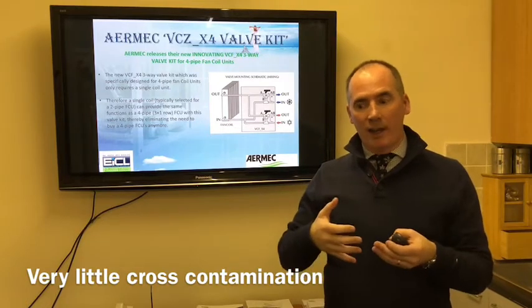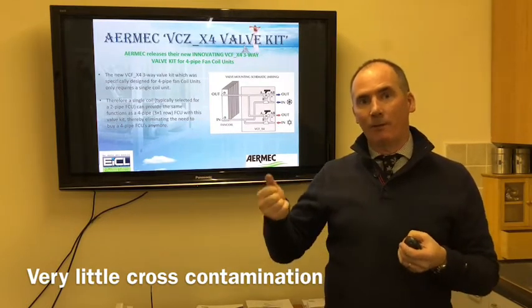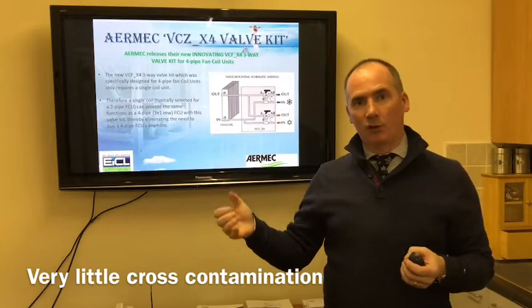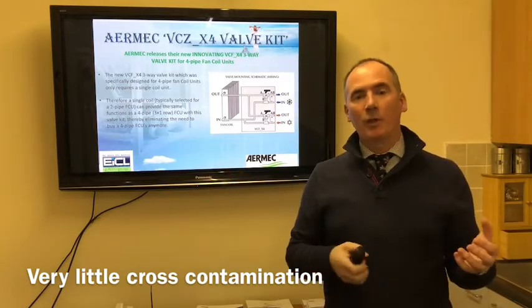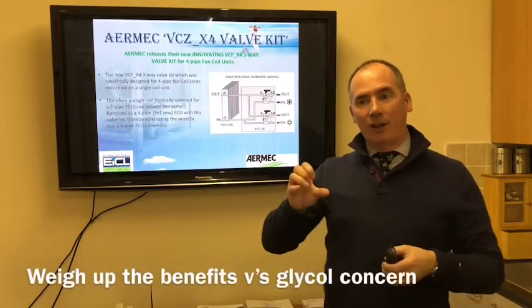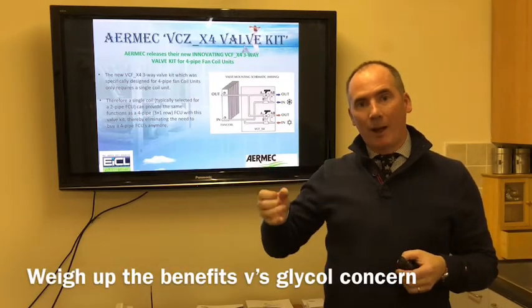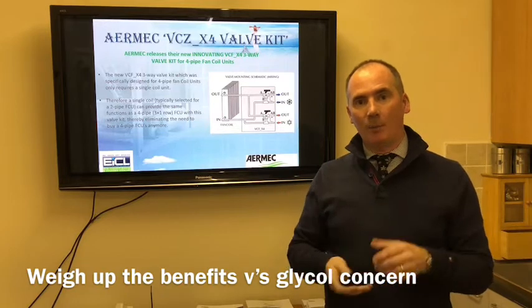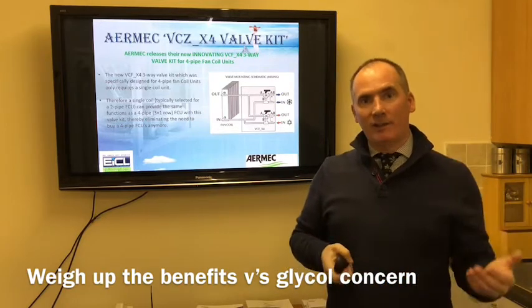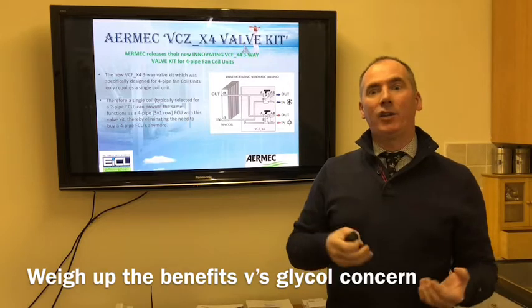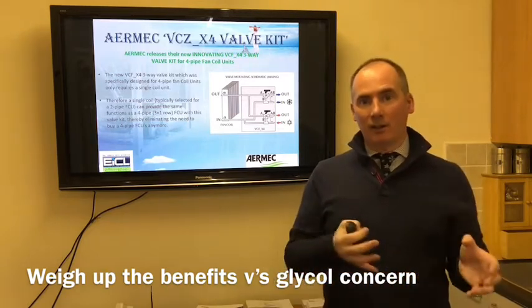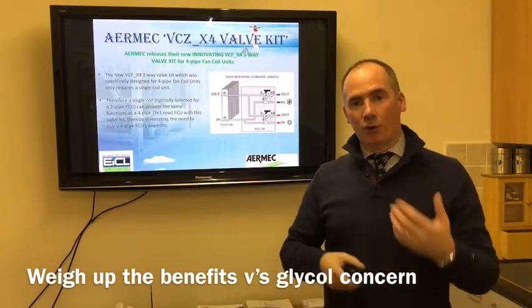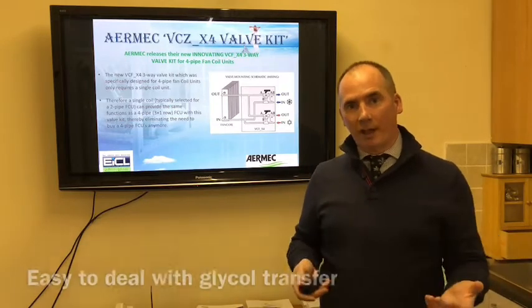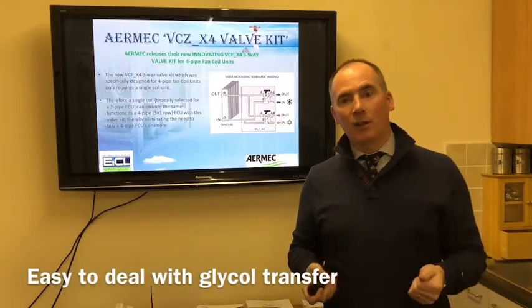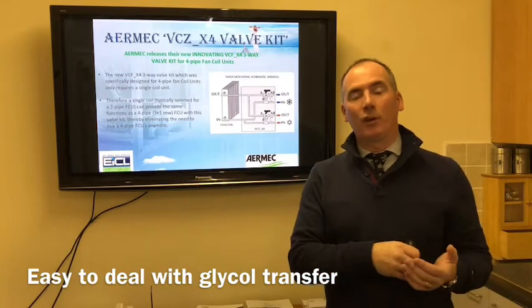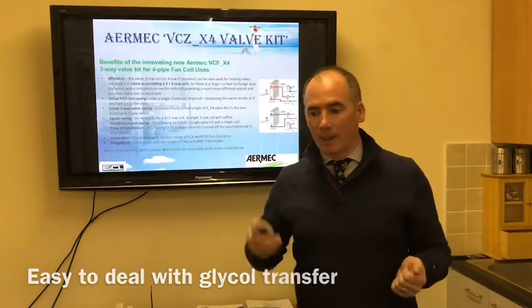It's not regular, because you will have the same valve opening and closing pretty much for the whole summer, and the same other valve opening and closing all winter. Obviously with the difference with the control band, it's not frequent, it doesn't happen too often. If you consider the downside of that occurring, weigh it up with the efficiency savings, the glycol situation becomes pretty much negligible, and of course you can account for that. Either design your system without glycol, or just implement a maintenance schedule where you keep an eye on it. Quite simple, look after that.